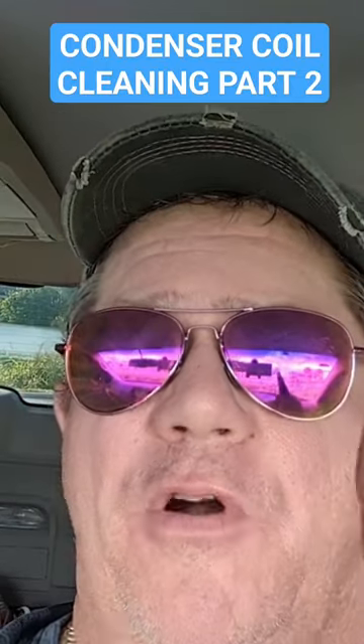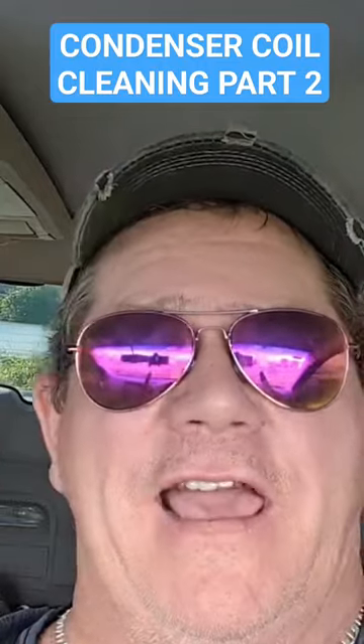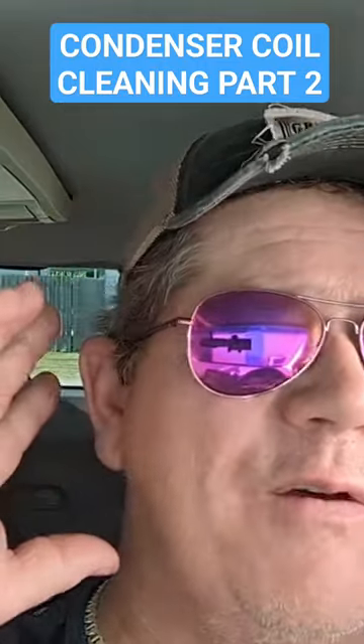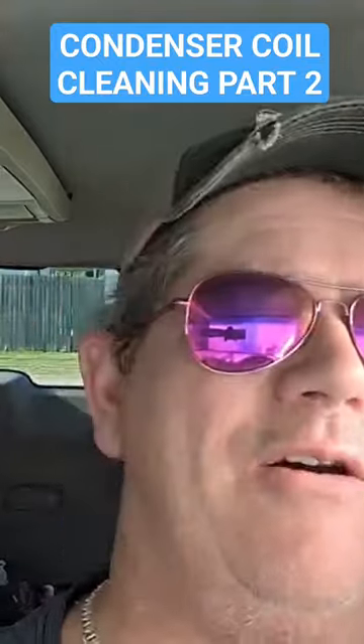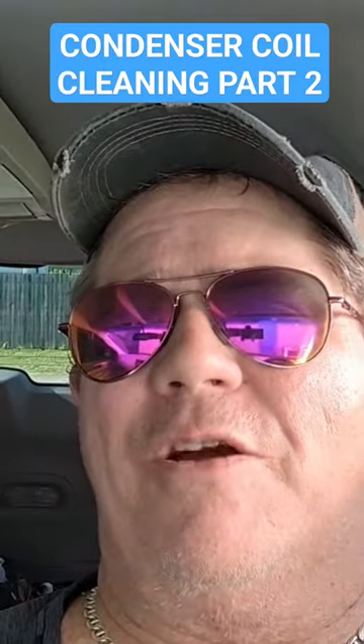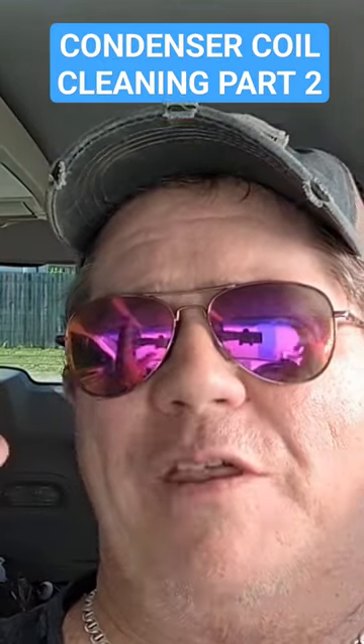I recently made a video for homeowners on how to lightly clean their condensing coil and I nearly got dragged for that. Some of the guys were saying, hey man, you got to take this whole thing apart and clean it from the inside out. Residential air conditioners — most of that is a bunch of hooey. I'm not going to wet sand and buff the paint job and put pinstripes on it and all that to do a how-to video for homeowners.